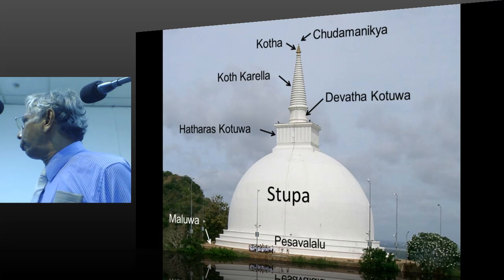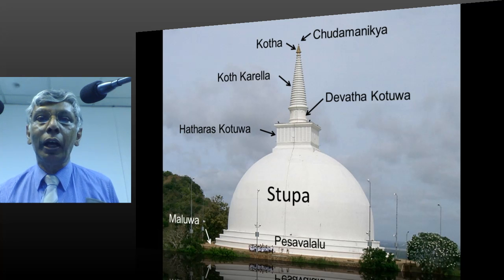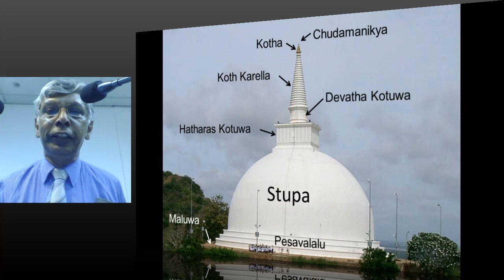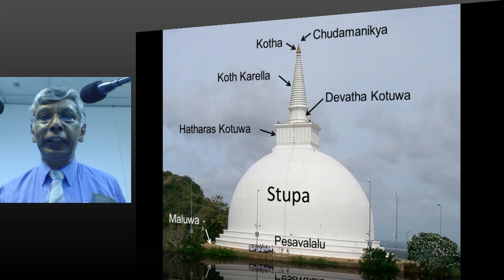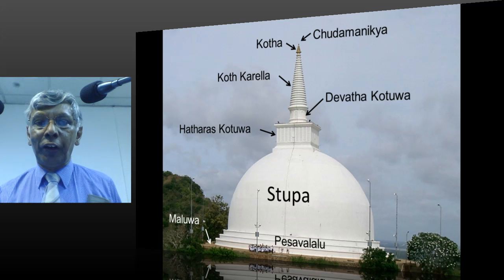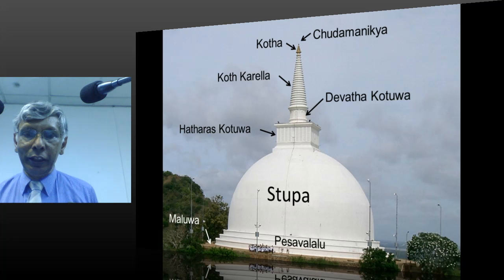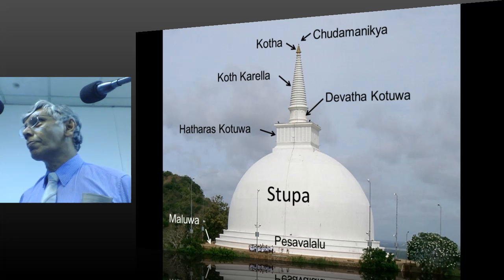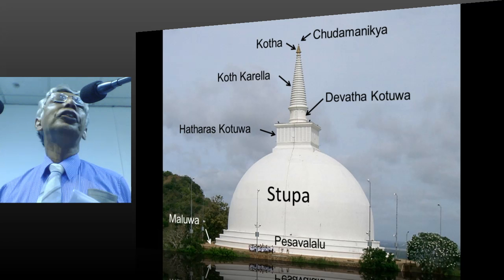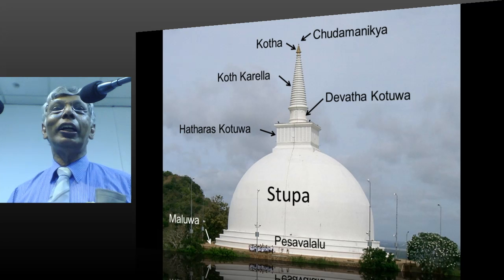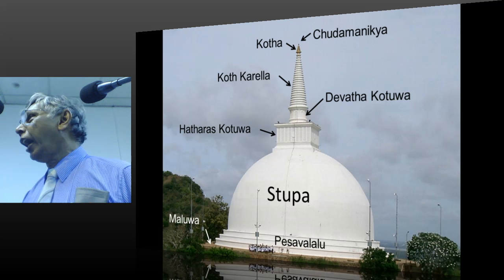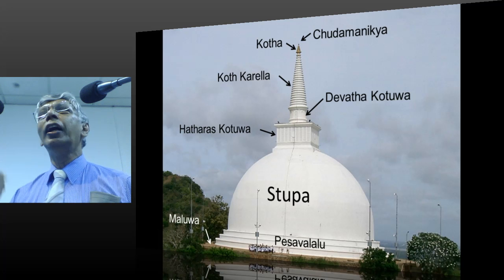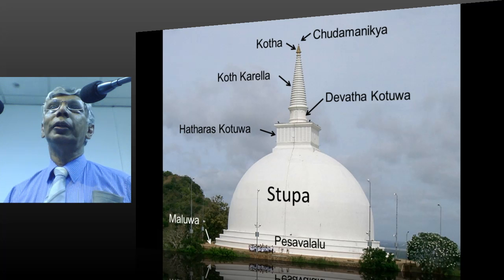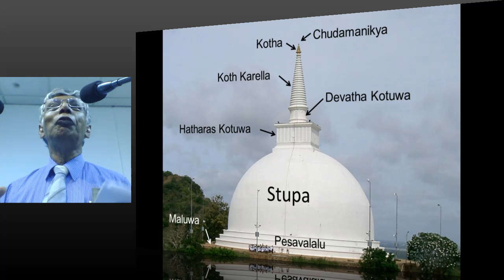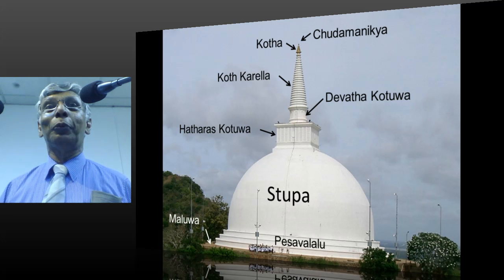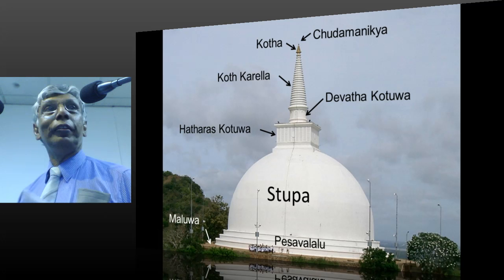You can also see the lightning conductor is not seen here. A present lightning conductor is here. The earth wire is running down like that and to the earth here. This is one of the worst things to do. In fact, I have gone with the TRC and even informed the prelate there that this is not a satisfactory arrangement. People think that if you put some sort of lightning protection, it's lightning protection. What is wrong with this?